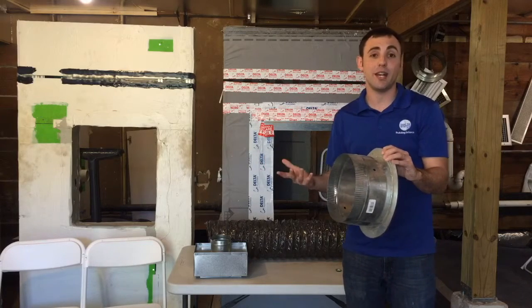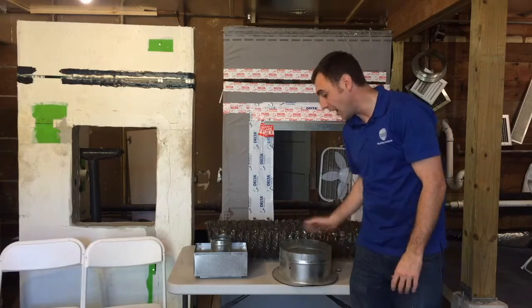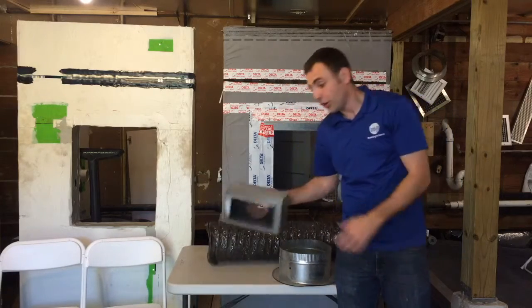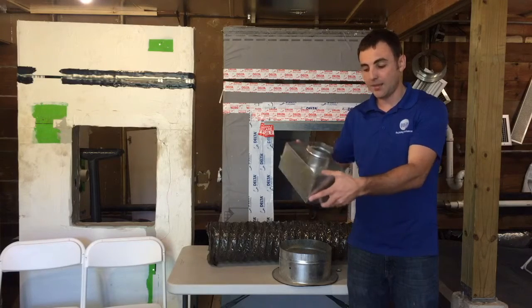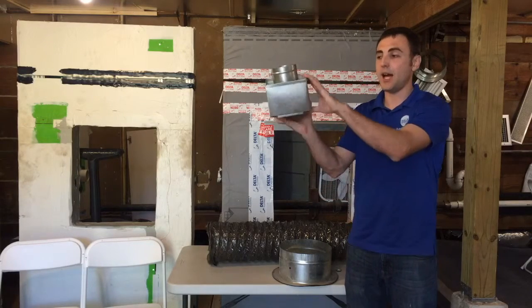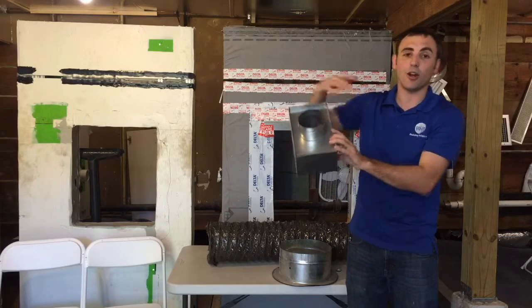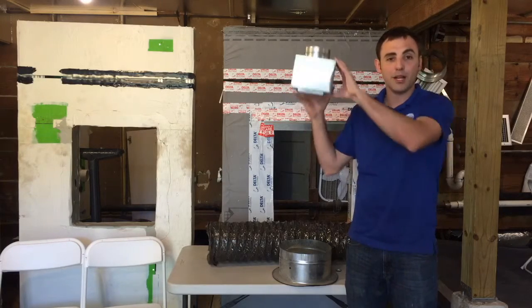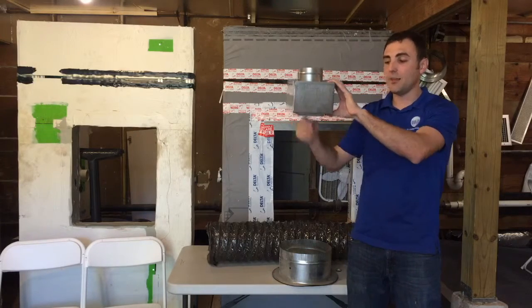Because another thing you want to take into consideration is noise. If you were to not damper here and damper closer to the unit, closer to the room, in the back of this supply duct right here, you could put a little tiny damper inside here. And the problem with putting a damper in the supply boot is this is going to increase the velocity coming through here.